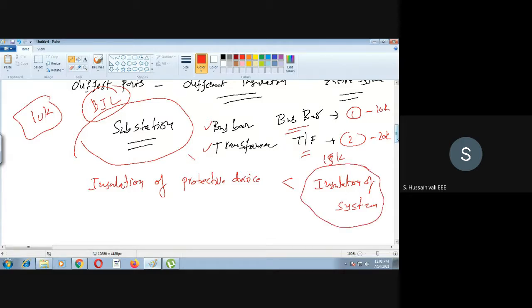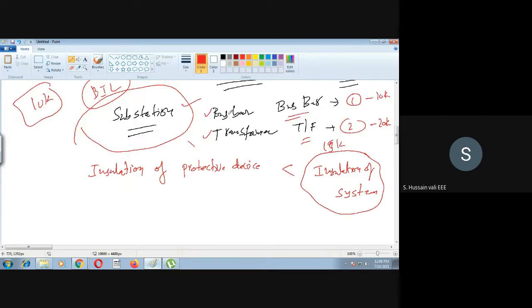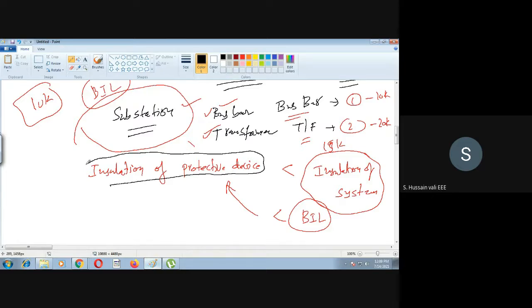Now every system has different equipment. I said, you take the case of the substation, you have bus bar, you have transformer, and both have different insulation levels. Then how do we know the insulation level of the system? Then we will have this BIL, the basic impulse insulation level of this system. This should be greater than the protective device insulation. So when we want to select a particular protective device, we need to know its insulation level, and also the insulation level of the entire system, which is nothing but the BIL. Every system has this BIL value, and the protective device insulation should be less than the BIL of the particular system.